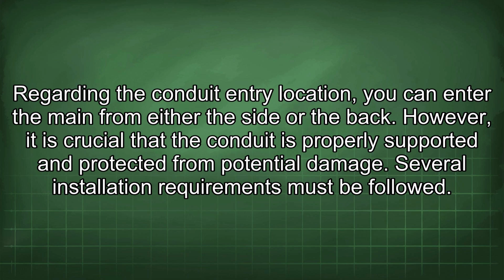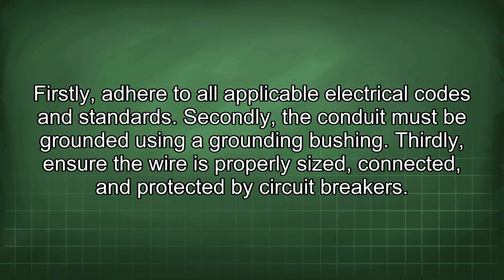However, it is crucial that the conduit is properly supported and protected from potential damage. Several installation requirements must be followed. Firstly, adhere to all applicable electrical codes and standards. Secondly, the conduit must be grounded using a grounding bushing. Thirdly, ensure the wire is properly sized, connected, and protected by circuit breakers.